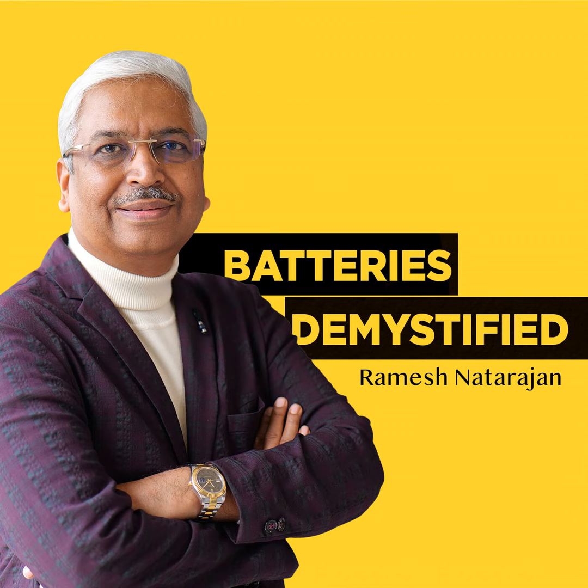As far as hydrogen evolution is concerned, nowadays there are sensors which are available from various sources and there are many companies making these sensors. These sensors are of a nature wherein it is possible to put on the fans only if the hydrogen level goes beyond 1% or 2% in a battery room. So they save on electricity also. You don't have to keep the exhaust fans continuously on in a battery room.